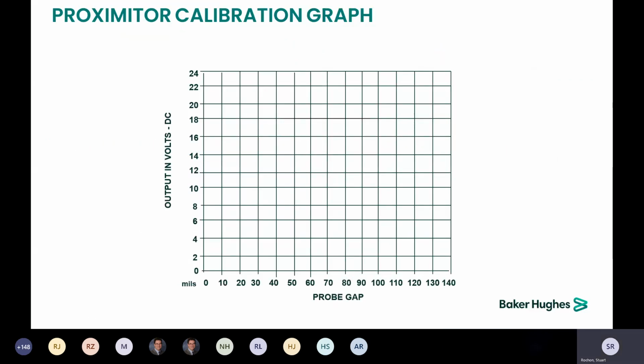Now, we do recommend that you run a calibration on your proximity probes once a year. We also realize that you guys are in the business of making money, and to make money, you've got to have the machines running, and you're not going to take them down every year just to check the proximity probes. So we do recommend that you check them anytime that you have access to the probes.